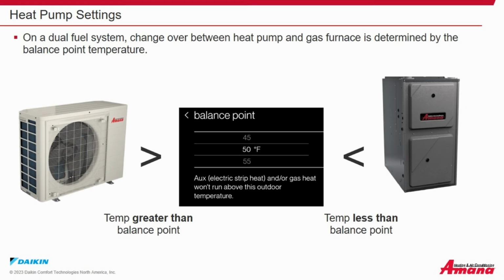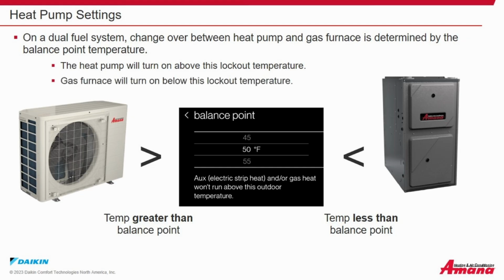Heat pump settings. On a dual fuel system, changeover between heat pump and gas furnace is determined by the balance point temperature. The heat pump will turn on above the lockout temperature. The gas furnace will turn on below the lockout temperature. If your balance point was set to 50 degrees Fahrenheit, above 50 degrees Fahrenheit, the heat pump would operate. Below 50 degrees Fahrenheit, the gas furnace would operate.